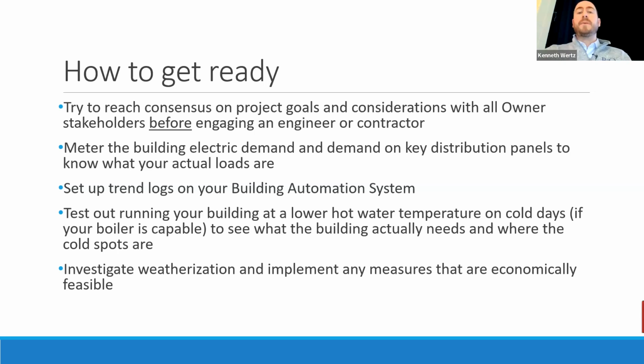Next one here, if you do have a building automation system, I would highly advise you to be storing historical data from that system for as long as you can. I know they don't always have unlimited capacity for storing data, but as much as you can is all the better, because again, you're making a more informed decision. If you're worried about being able to maintain a warm enough temperature in certain parts of the building, or you're worried about how often your boiler needs to run at night, or do you need both boilers over the winter or just one boiler, et cetera.